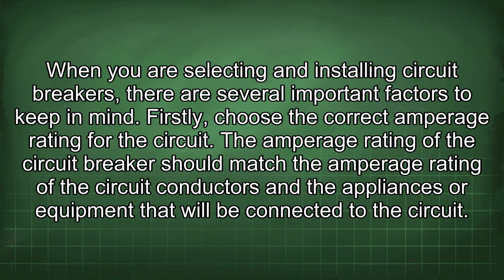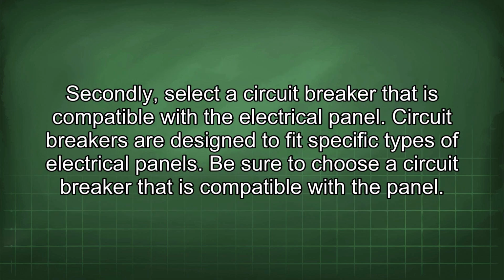When you are selecting and installing circuit breakers, there are several important factors to keep in mind. Firstly, choose the correct amperage rating for the circuit. The amperage rating of the circuit breaker should match the amperage rating of the circuit conductors and the appliances or equipment that will be connected to the circuit. Secondly, select a circuit breaker that is compatible with the electrical panel. Circuit breakers are designed to fit specific types of electrical panels. Be sure to choose a circuit breaker that is compatible with the panel.